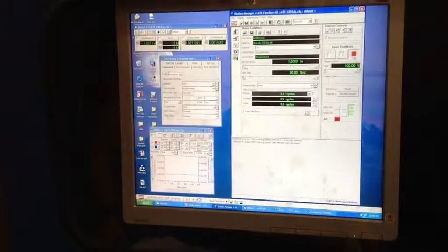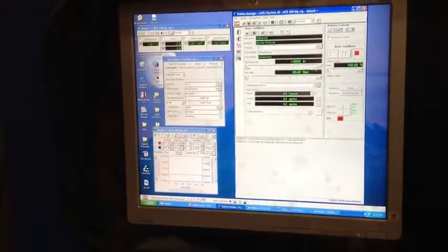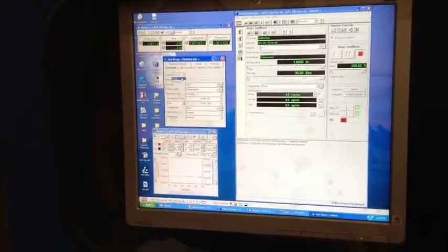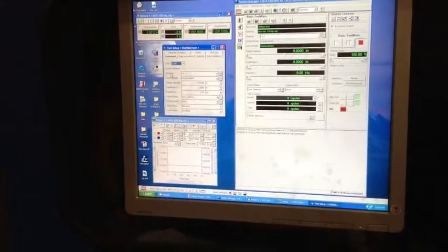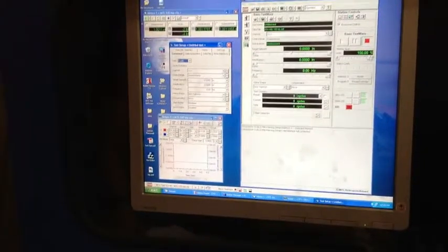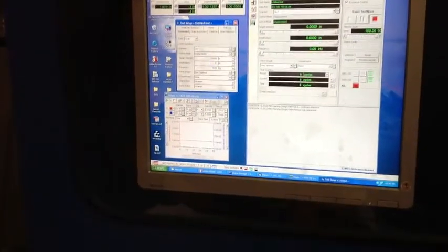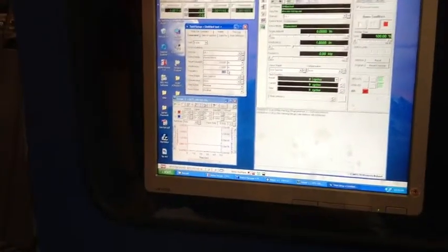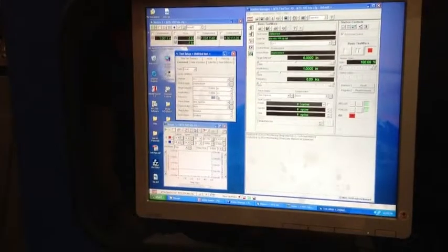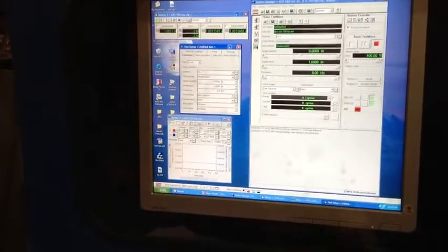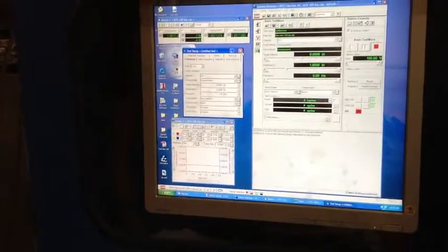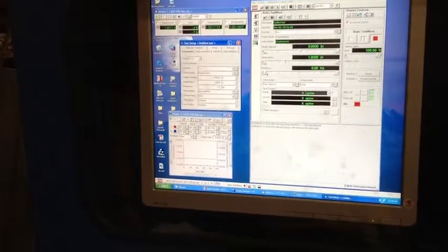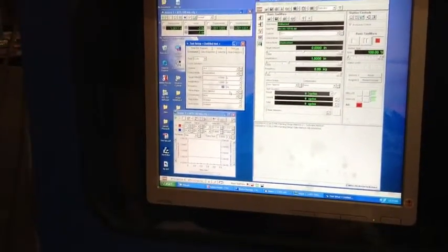And just in case you want to do some cyclic test, you change the test type in here to cyclic. And you don't change your channel number and you don't change your control mode. And in the amplitude, you can put in 1.0. And in frequency, to start with, I would encourage you to start with some really small numbers, such as 0.5. In fact, 0.5 Hertz is pretty large. Then you click enter.